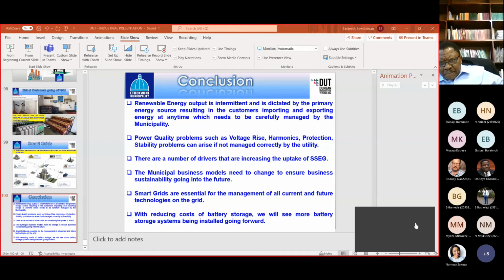First one: we don't allow the customer what we call anti-islanding, meaning his PV system has to switch off when the grid switches off. But what happens is, like those guys with diesel generators, they have a changeover switch, where the load can only be fed from the grid or from the diesel generator, not both. So there's no risk of feeding back to the grid.